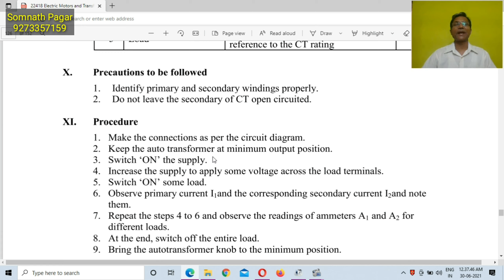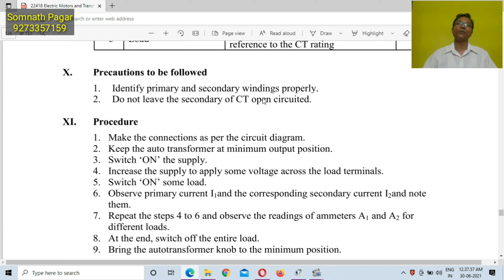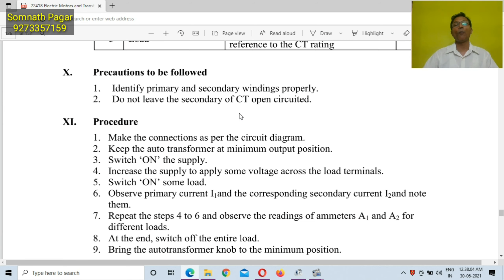While performing this practical, you should follow some precautions: identify the primary and secondary windings properly. You must be able to identify the windings of the CT. Do not leave the secondary of CT open circuited — you should never leave the secondary of the CT open circuited.